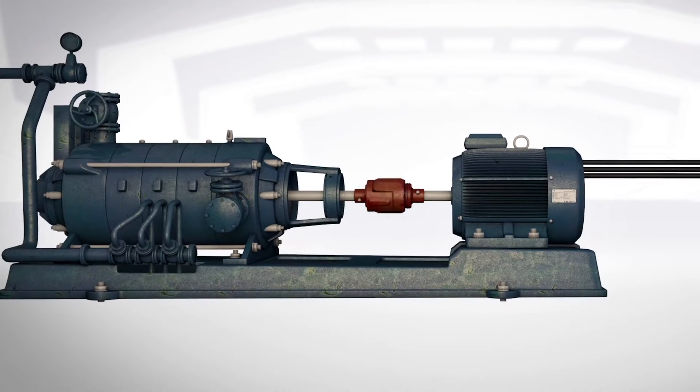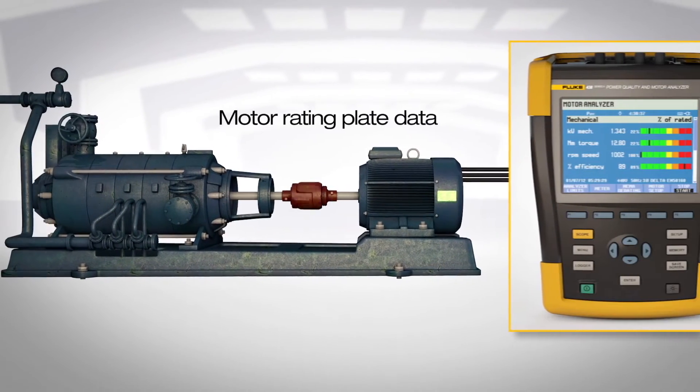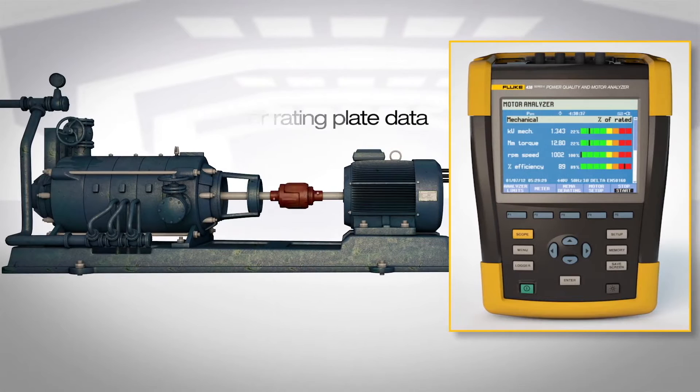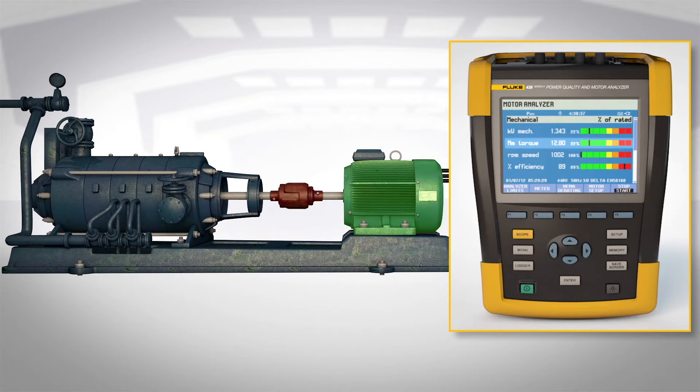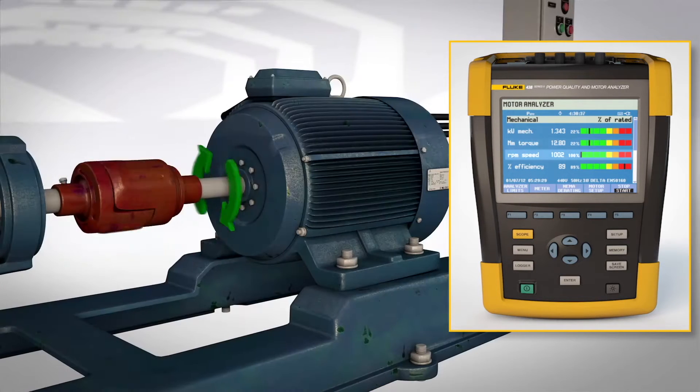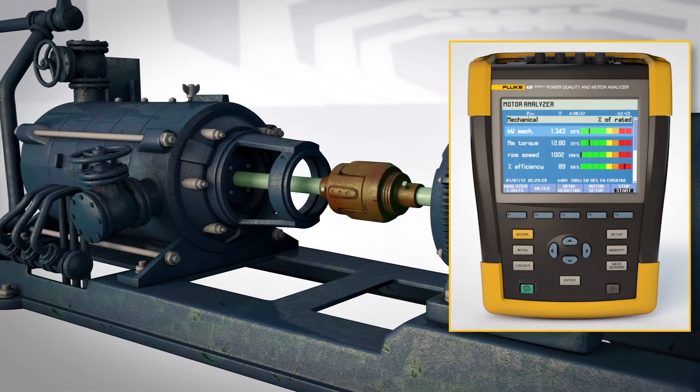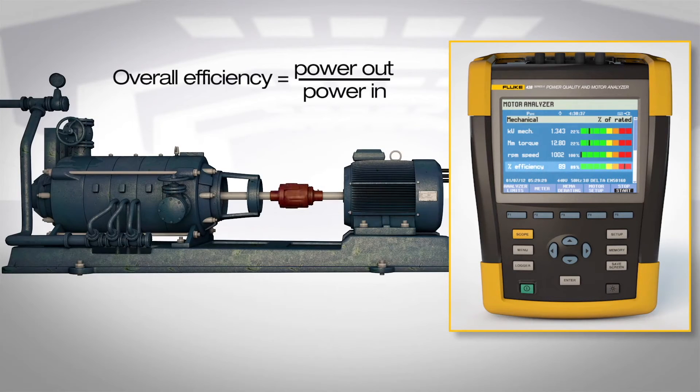Using three-phase electrical measurements on the input and motor rating plate data, the 438 calculates torque, the most critical mechanical performance variable, speed, load on the motor shaft and overall efficiency without the need to install mechanical sensors.